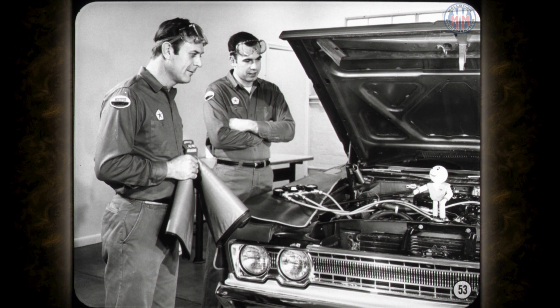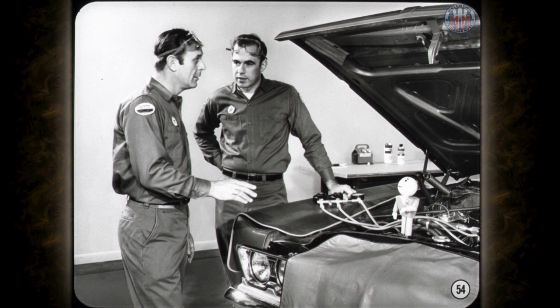Tom, just remember that these have all been preliminary pressure checks to alert you to possible trouble causes. And now it's time to review the service manual procedures for checking the expansion valve, the EPR valve, and the compressor. Ready, Fred? Ready, Tech. And here's what you do. First, make sure the refrigerant level is correct, so pressure test indications will be dependable.